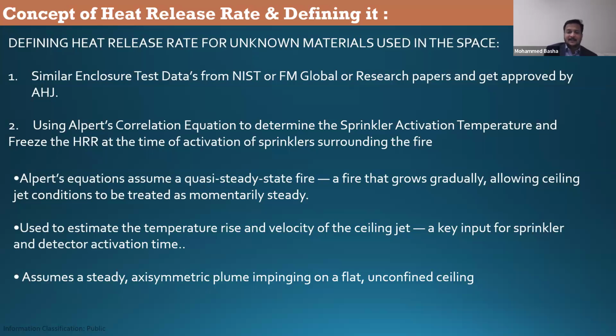Alpert is a gentleman engineer like us. He created some equations to determine the ceiling jet airflows and the activation temperature of sprinklers. Alpert's equation can be used for steady state fire as well as T-squared fires. It assumes a quasi steady state fire, because I want to discuss with you the T-squared fire, which is called quasi steady state. It is a fire that grows gradually, allowing ceiling jet conditions to be treated as momentarily steady, used to estimate, this is the important thing, the temperature rise and velocity of the ceiling jet, a key input for sprinkler and detection activation time.